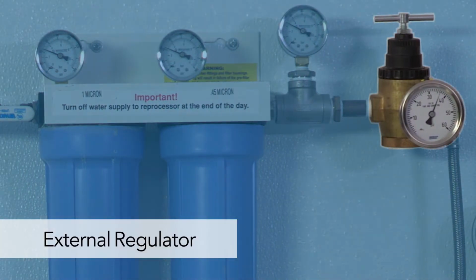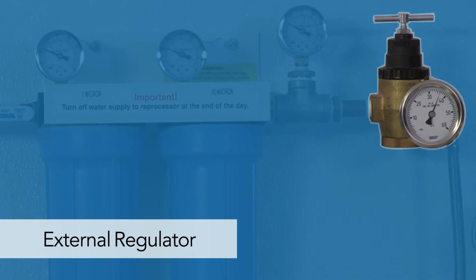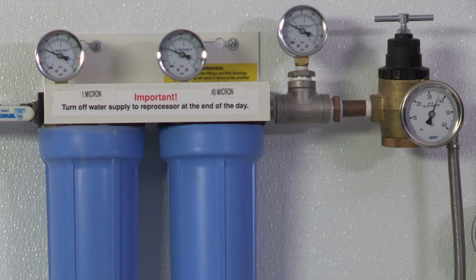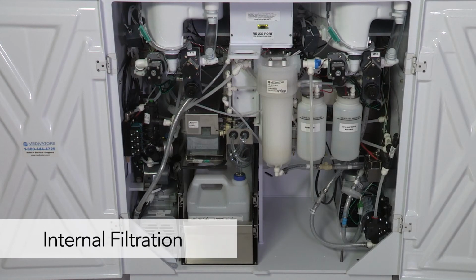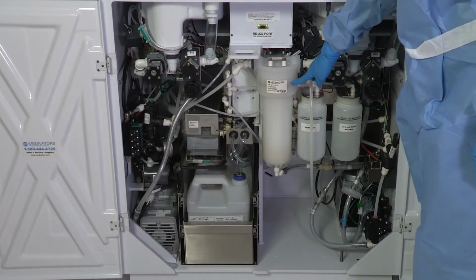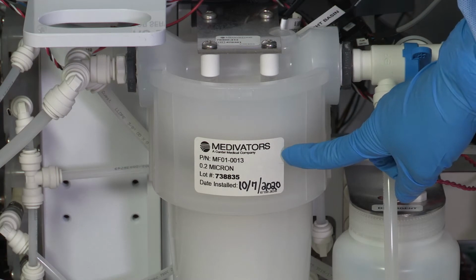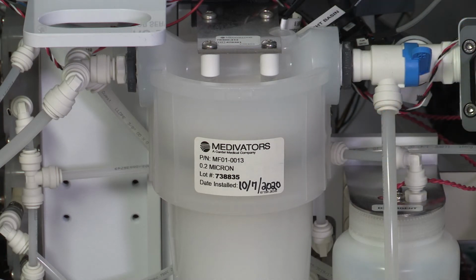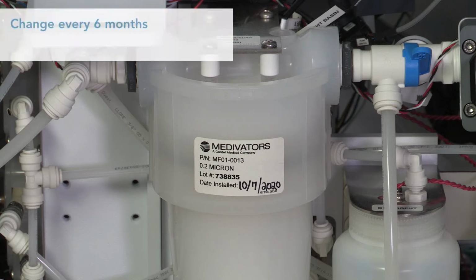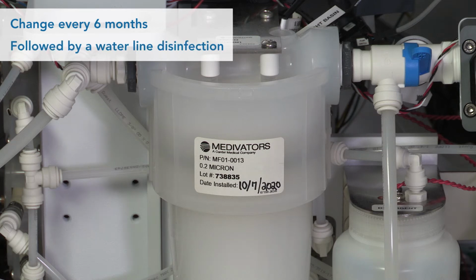An external regulator controls the pressure of incoming water to the DSD EDGE Reprocessor to ensure it does not exceed 35 to 40 psi. This is set during installation by your Medivator's Field Service Engineer, or FSE. The internal 0.2 micron absolute rated filter removes and retains bacteria from the rinse water. To assist in keeping your system free of microorganisms, this filter must be changed every 6 months, or more frequently, depending on the water quality in your area, followed by a waterline disinfection.